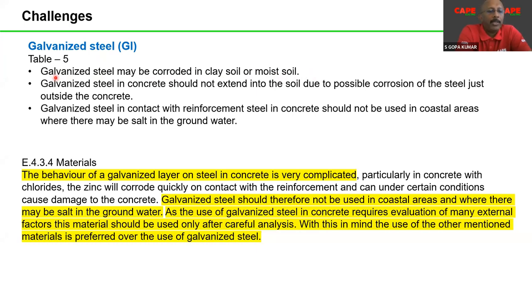If the galvanized steel GI strip or GI conductor put under the building corrodes within 10 years or 20 years or 30 years, after 20, 30 years you have nothing on the ground. So you will be in deep trouble. So galvanized steel may be corroded in clay soil or moist soil. So while using natural components, you have to think twice about using GI. Galvanized steel in concrete should not extend to soil due to possible corrosion from steel just outside the concrete. I have a picture I will show you.